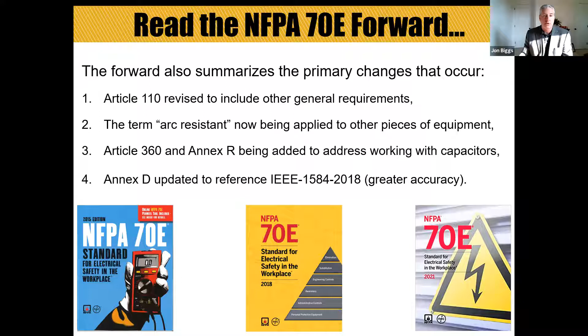Annex D was also updated. We won't talk a lot about this since it really involves engineers, suppliers, outside vendors, or engineering firms that provide an incident energy analysis for your work area. What's been updated is the IEEE 1584 standard—now in its second edition, the 2018 edition—which provides much greater accuracy on our arc flash studies and incident energy analysis, whether done in-house or by an outside firm. We're seeing significant improvements in accuracy based on those changes.